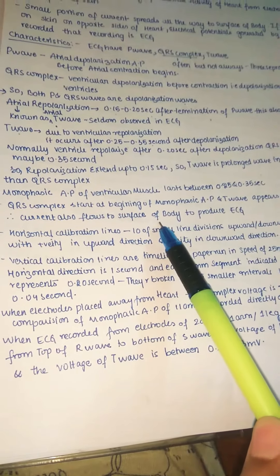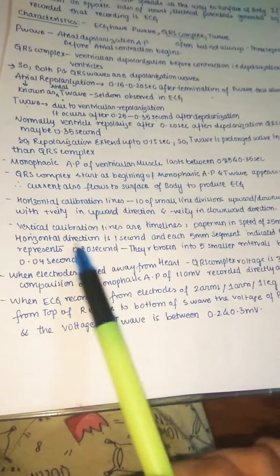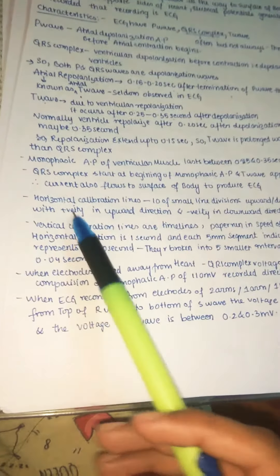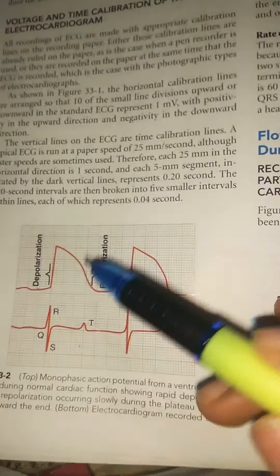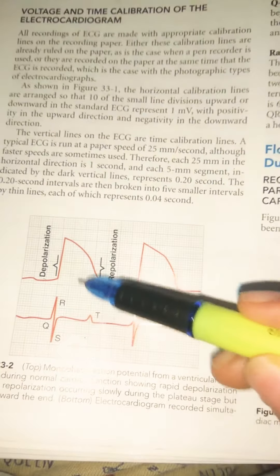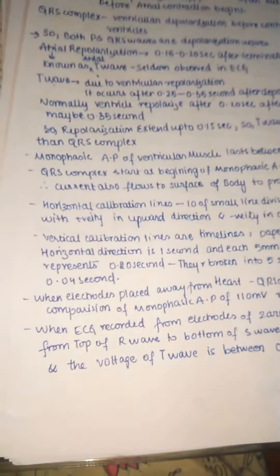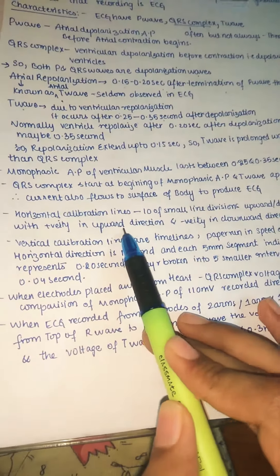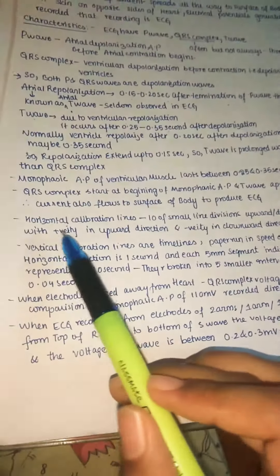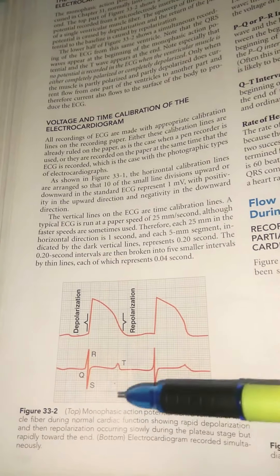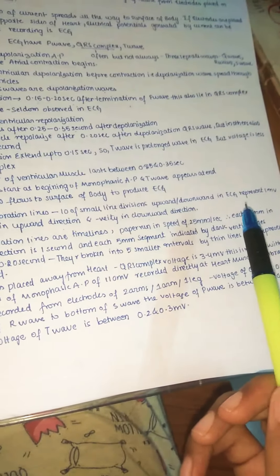The current flows to the surface of the body via body fluids to produce the ECG. Now let us observe the ECG paper. The horizontal calibration lines: there are 10 small line divisions upward or downward, representing one millivolt. Positivity is in the upward direction and negativity in the downward direction. The vertical calibration lines are the timelines representing time.